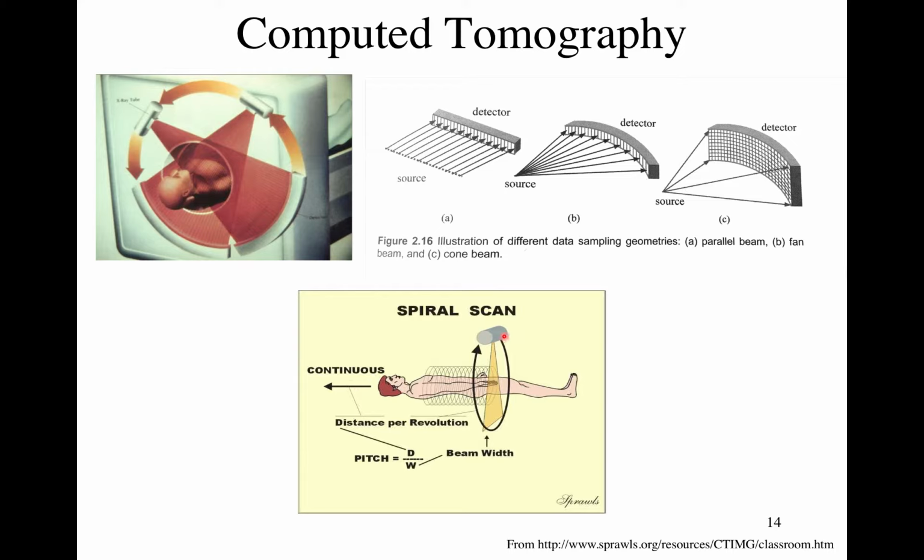One of the big deltas in CT technology occurred when, instead of having a system where I start my detector here, rotate it once and stop, because I have cables, I have a whole bunch of signals coming from this detector, and they're coming out on cables. So I have to rotate the thing once, stop, then rotate it back, because you can't tear the cables up.